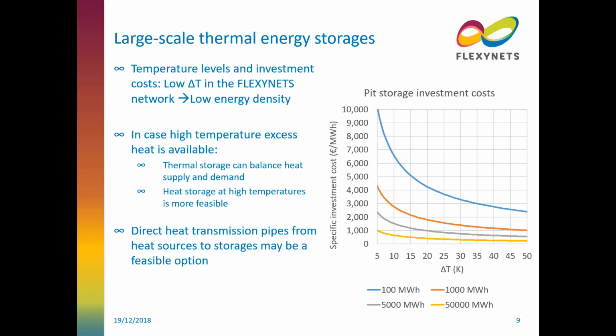One of the drawbacks of the FLEXYNETS concept in terms of these storages is the low delta T. If you have one cubic meter of water, it's very important how big the temperature difference is when considering how much energy you store. The smaller the delta T, the lower the amount of energy you have in a specific volume. So it's a relevant technology to include in the FLEXYNETS concept, but it becomes more relevant and feasible if you have access to somewhat higher temperatures, for example waste heat you can use directly in the storage. We also noticed that if you have higher temperature waste heat, instead of injecting it into the network and applying seasonal storage connected to the network, you might be better off connecting the seasonal storage with the high temperature waste heat source directly.